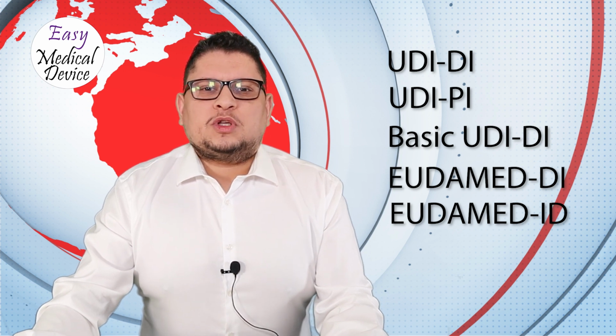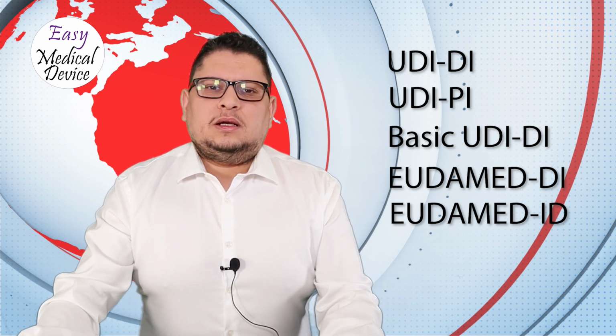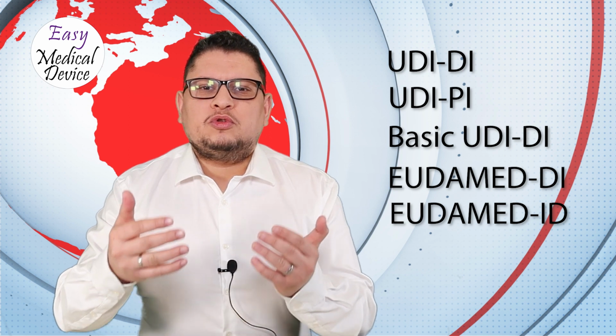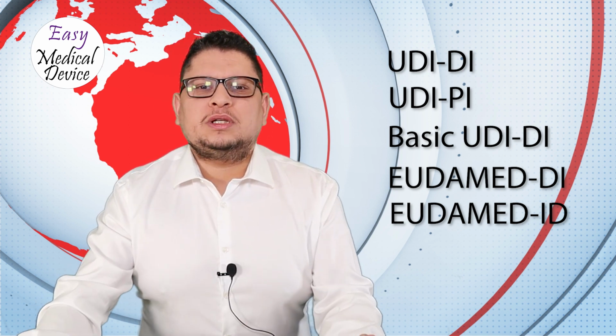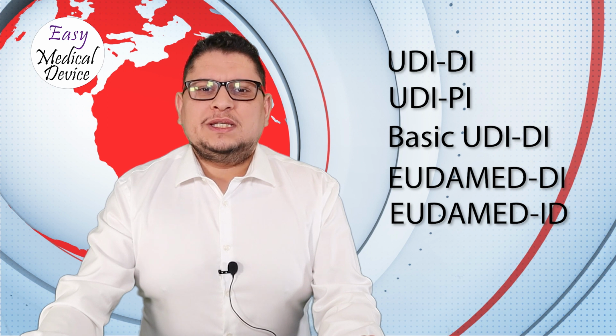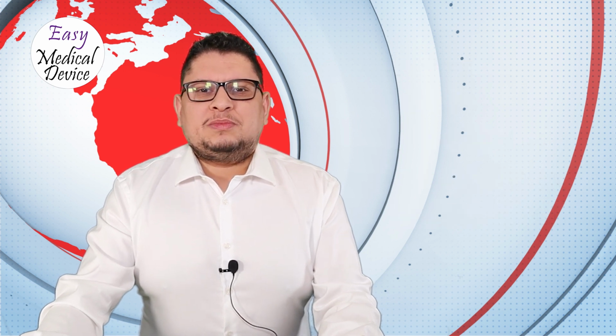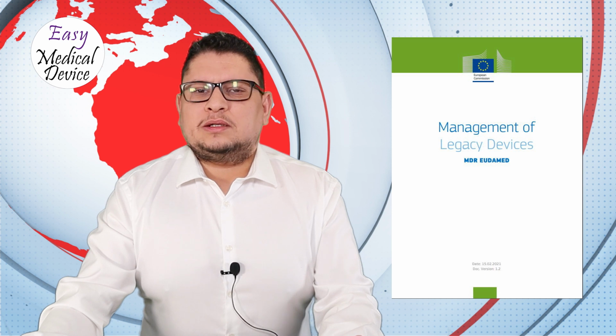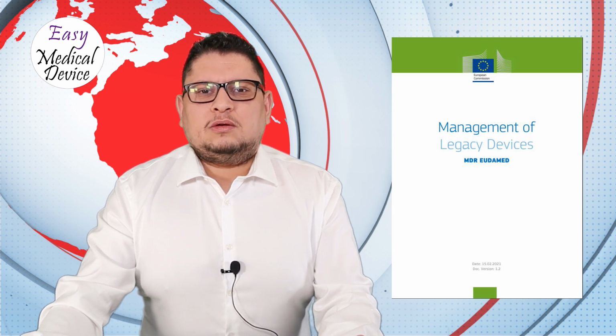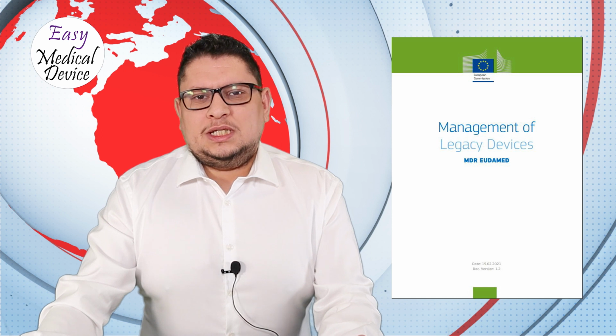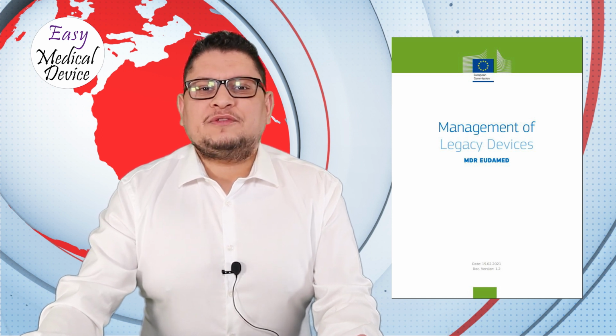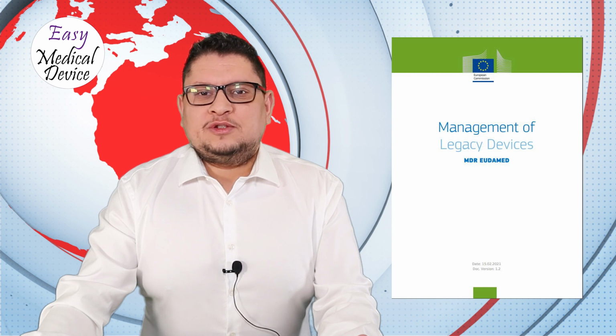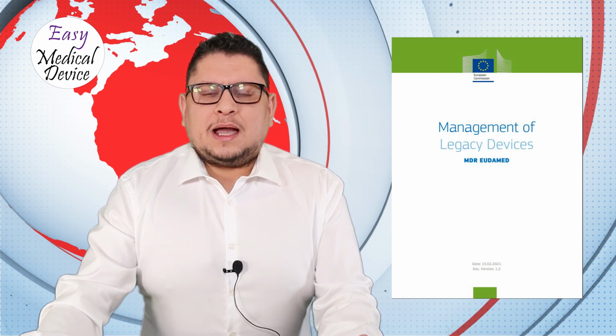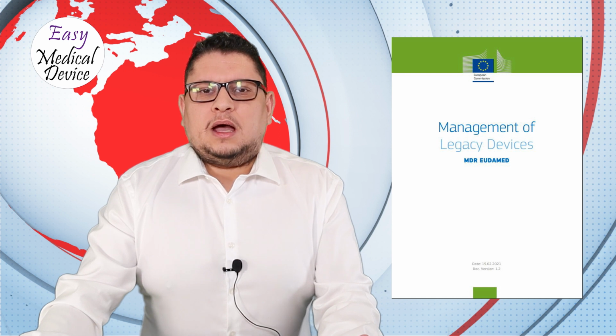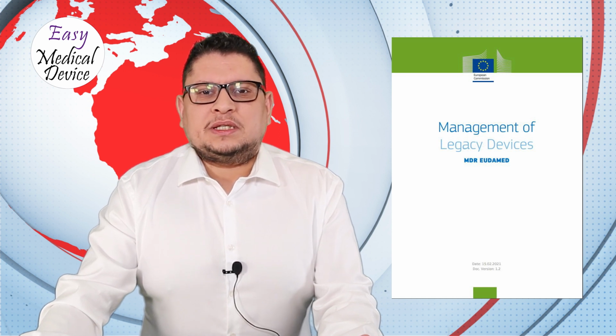There are also some rules for when you will be moving from MDD to MDR, on how to still link those two products, the legacy product and the EU MDR product, without losing any of the history. So you can go to this document. It is in the show notes, and you can review it and check exactly what will happen. Don't wait for an issue to happen on the market after the date of application to read this document. Start to understand now what the rules are and how you can apply them when something is happening.